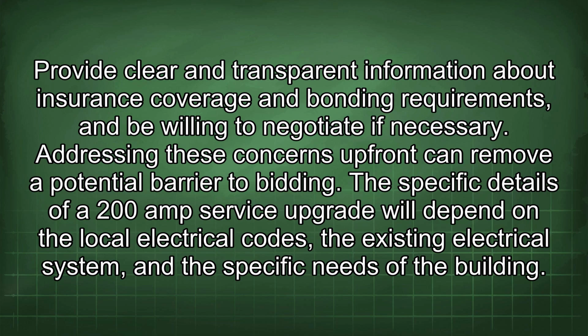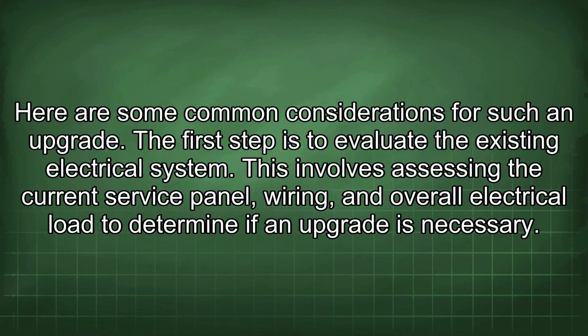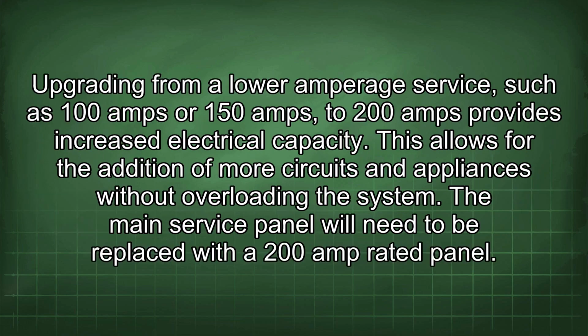The specific details of a 200 amp service upgrade will depend on the local electrical codes, the existing electrical system, and the specific needs of the building. Here are some common considerations for such an upgrade. The first step is to evaluate the existing electrical system. This involves assessing the current service panel, wiring, and overall electrical load to determine if an upgrade is necessary. Upgrading from a lower amperage service, such as 100 amps or 150 amps, to 200 amps provides increased electrical capacity. This allows for the addition of more circuits and appliances without overloading the system.